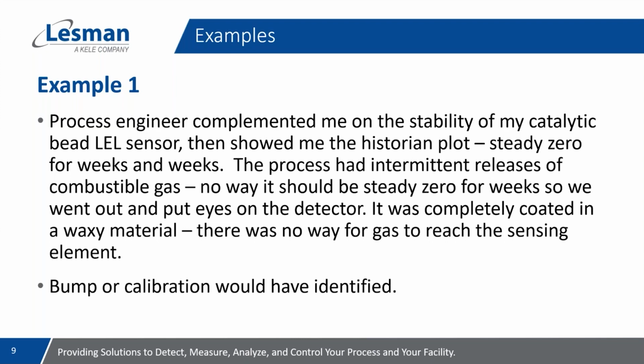So we ended up walking out to the site and we found that the sensing point that was solid zero on the data historian had a waxy buildup all around it. There's absolutely no way for the gas to get to the sensing element. The history here is that this company did have a very sophisticated calibration and maintenance program, but as we dug in a little deeper, the function had been transferred to a new technician. When the technician was out doing his rounds, he did not see the sensor because it was completely plugged up with wax, didn't look like a transmitter, and assumed it was a missing tag. So only putting eyes on the sensor could correct this or catch this.